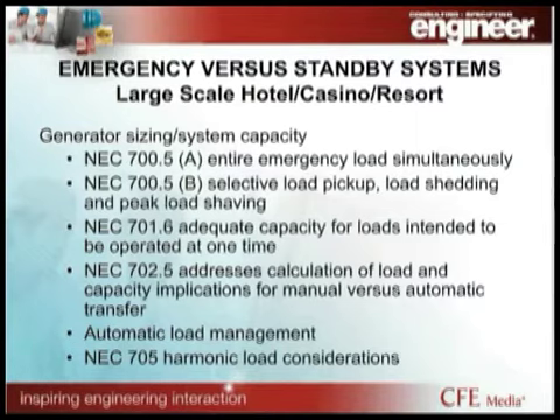Automatic load management is another thing that you can do with the aggregate system that is really beneficial. If you should lose an engine, you can actually, with real-time demand management, drop loads off that are the lowest priority to keep the system working. And when you're doing your sizing, and this is probably more for Gerald, it's much for me too, there's so much harmonic content that makes up a lot of the loads that go into these larger facilities. You really need to take a look at your harmonic load profile and what your harmonic generating devices and equipment are. What kind of filtration is in place on, say, variable speed drives? How are we mitigating the harmonic impacts of UPS power, which typically you're going to have on the generator?